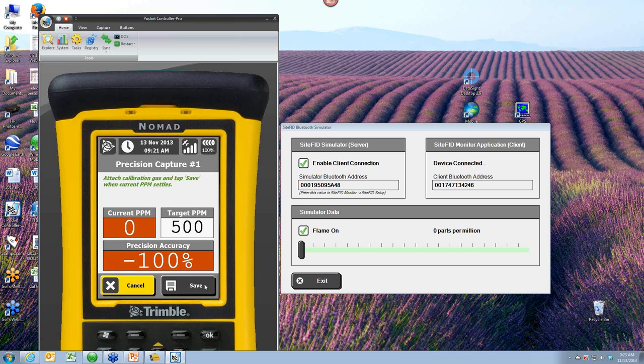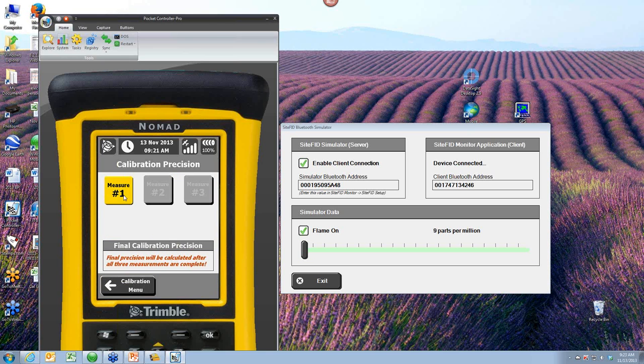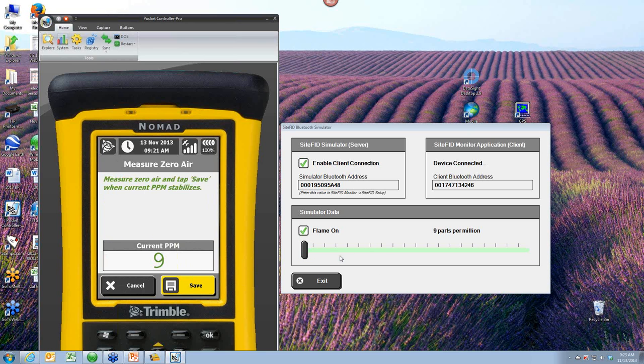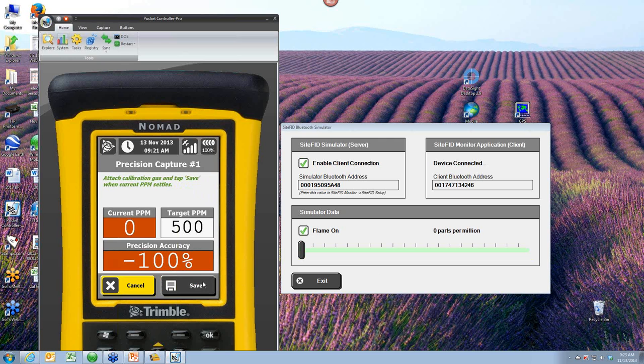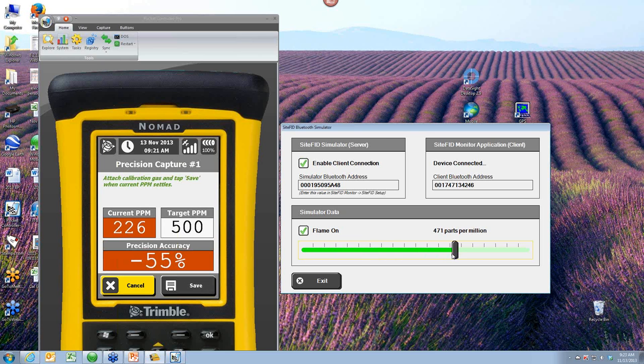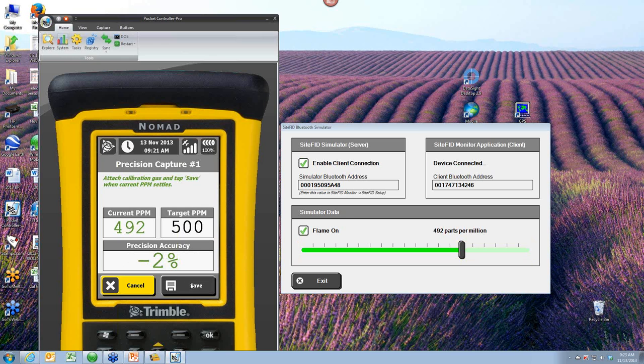The next thing it's looking for, oops, let me cancel that out. Hang on, let me try that again. So let's go ahead, and I'll put that on 0, hit save. Okay, now it's asking me to attach calibration gas. So this is where I'm going to trick it. I'll head up to 492, ought to work. We have to be within 5% plus or minus here. That's why you've seen this turn green. It was at red, now it's green.